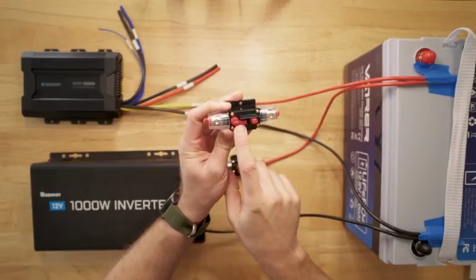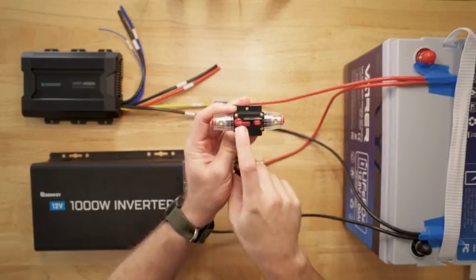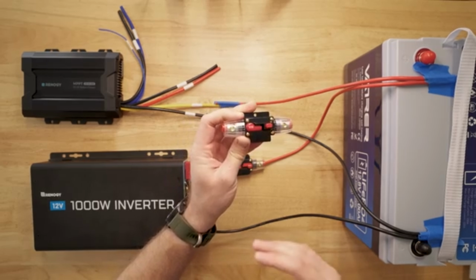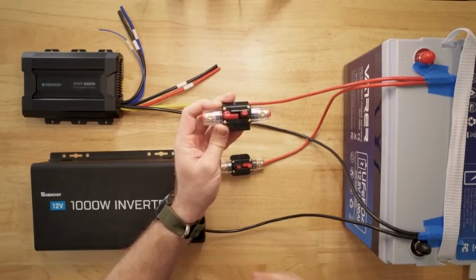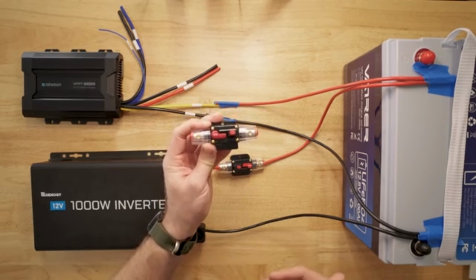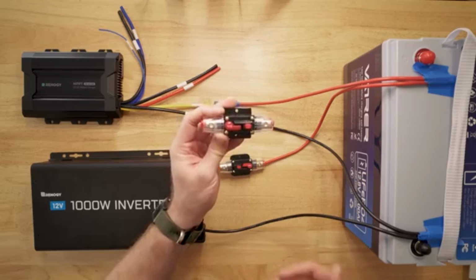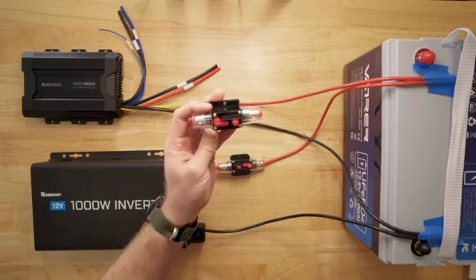The size or rating you need, in this case 60 amp, will vary based on the expected output of your DC to DC charger. You don't have to figure this out yourself — your manual should tell you exactly what fuse to use, and Renogy tells me to use a 60 amp.